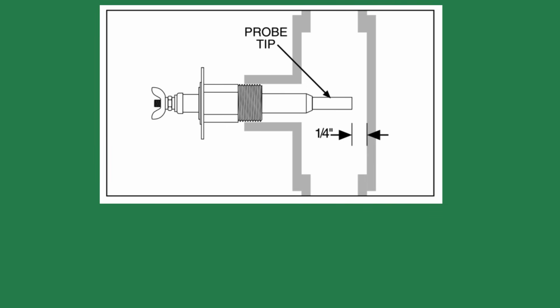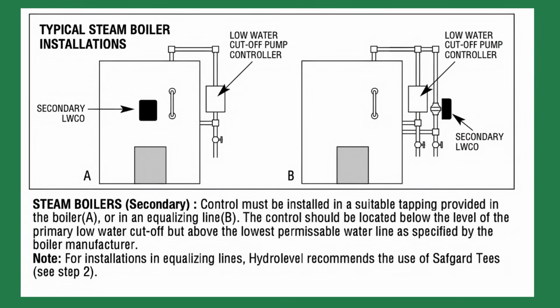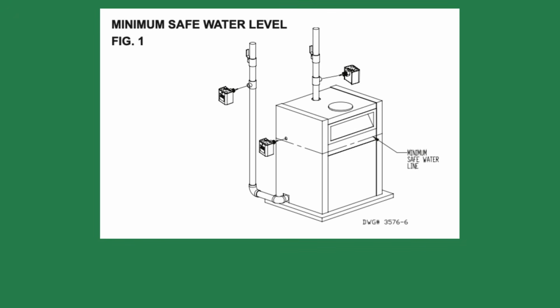When installing the probe into the boiler or fitting, most manufacturers require it to be a minimum of 1/4 inch away from the side of the pipe or any metal surfaces. The probe cannot touch the metal. On a steam boiler, the probe should be installed below the level of the primary low water cutoff, but above the lowest permissible water line, as specified by the manufacturer. For a hydronic boiler, you have more flexibility. It can be installed above the minimum safe water level of the boiler and even in the adjoining piping, as long as it's before any shutoff or isolation valve. Always check the manufacturer's minimum pipe dimension requirements for the probe location.